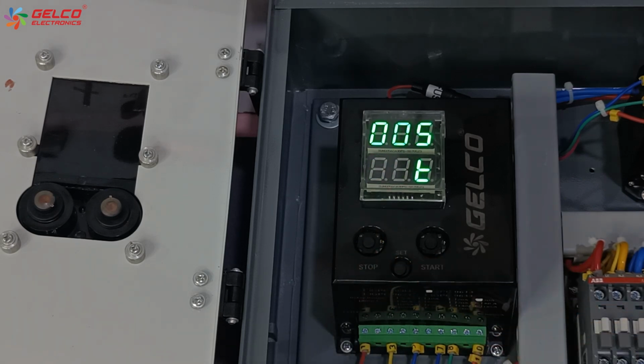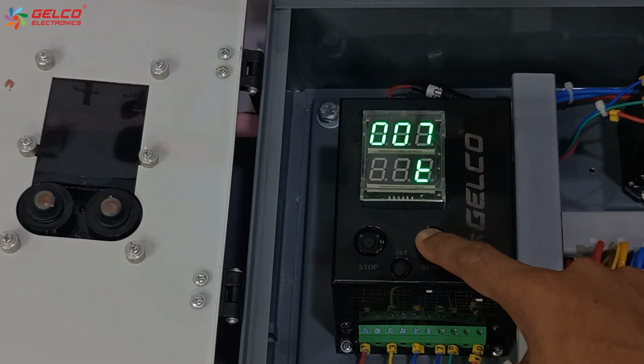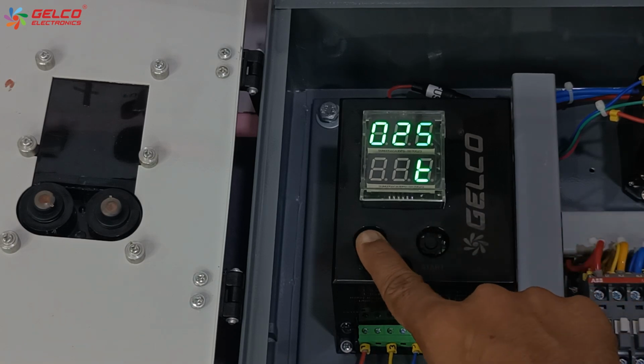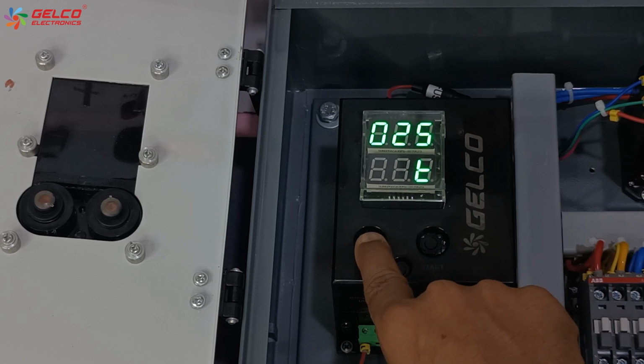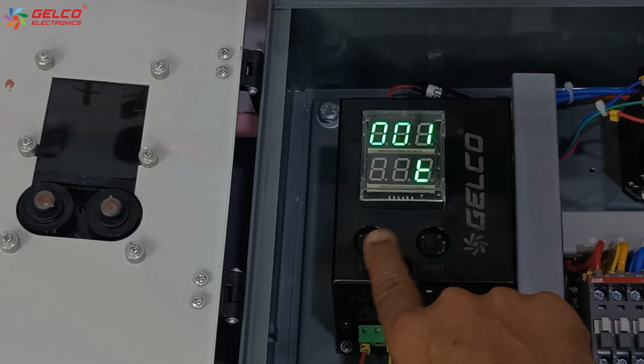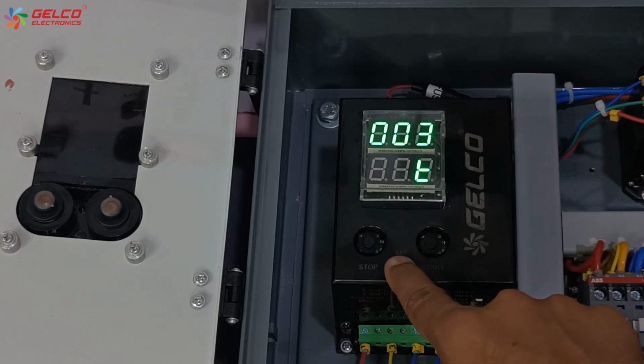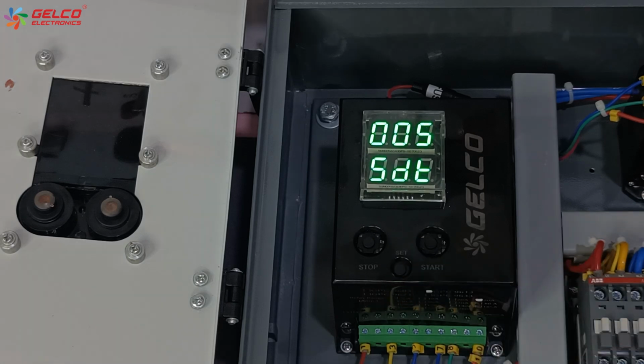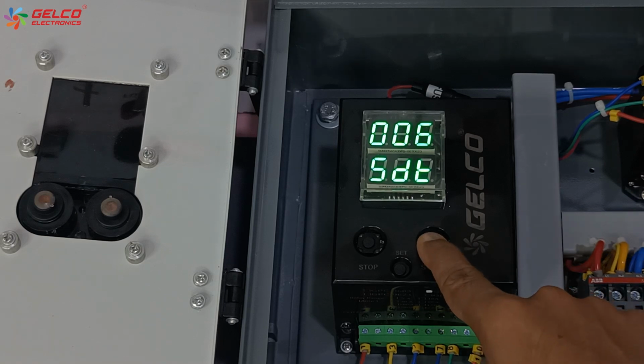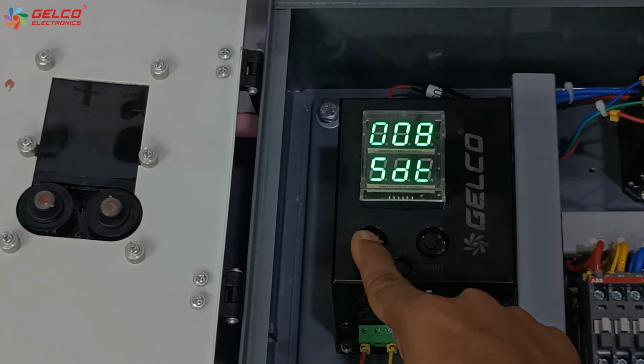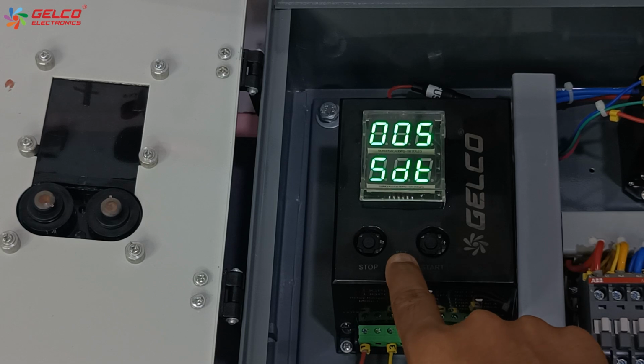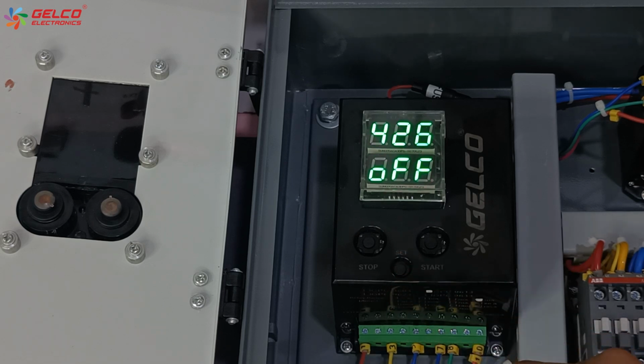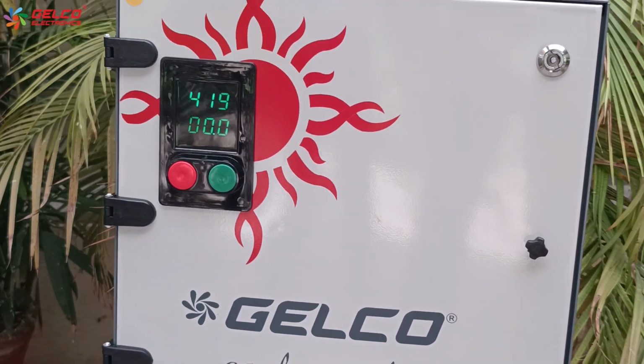Now time option will appear. In this we can set the time in minutes from the start and stop buttons. We can increase or decrease the value of time. After selecting the value, press the set button. Now StarDelta timer will appear. You can change its value by the start and stop button. After setting the value, press the set button. Now all the parameters are set in the panel.